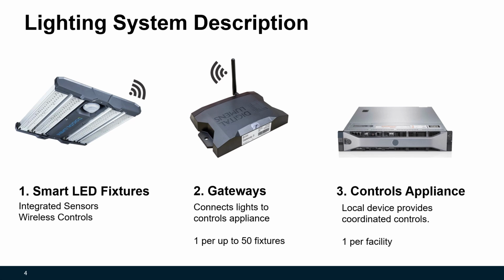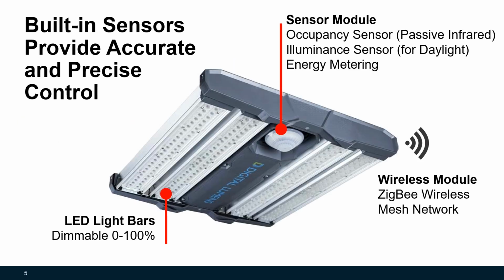Using a fully integrated system has key advantages in that you know the components will be compatible. Aftermarket lighting controls can be hard to design and implement, and fully integrated controls can simplify the process. Each fixture contains its own dedicated sensor module, including a passive infrared and occupancy sensor and a daylight sensor that measures the illumination on the work plane. LED light bars can dim from 0 to 100%, and a wireless Zigbee mesh network enables coordinated controls. Having sensors in every fixture improves the flexibility and performance of the system. This can greatly reduce user frustration. You've probably been in a room where the lights turn off because a sensor can't see you. This happens much less often when every fixture has its own sensor.